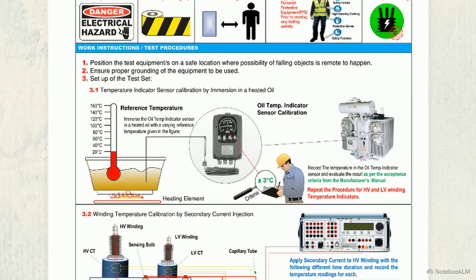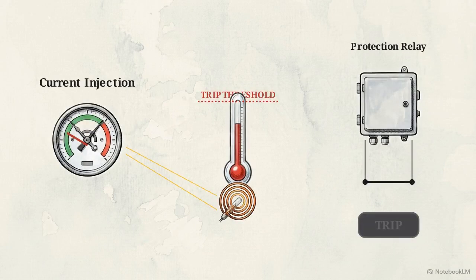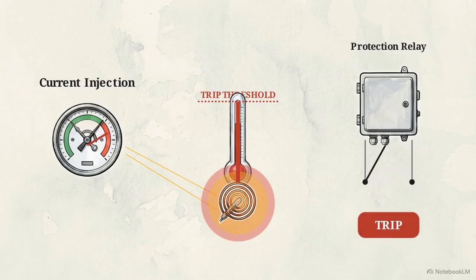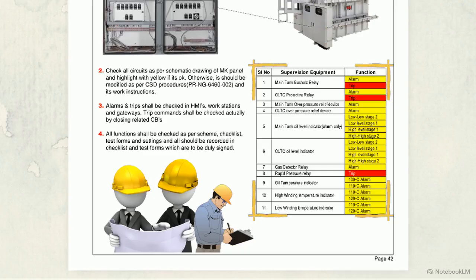We place the sensing bulbs into a controlled immersion oil bath, verifying that the local gauges read within 3 degrees Celsius of the reference standard. For the winding temperature indicators, we use secondary current injection into the heater coils, simulating the internal heat rise generated by load current to verify precise trip thresholds. This reference table maps the supervision functional checks.